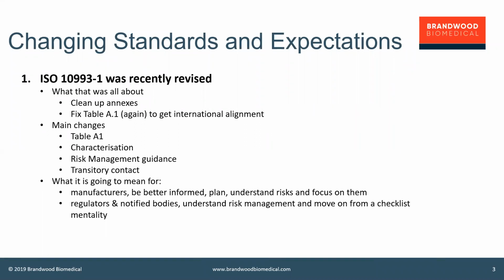Regulators and notified bodies really need to understand this as well. There's a lot more in Part 1, and there's a lot more coming in some of the other parts. It's not about just increasing workload. It's about the risk management model. It's about knowing what's important, what it is you're dealing with, and focusing on that in your reviews of technical submissions, not just having a very long list and asking have we done all of these things.